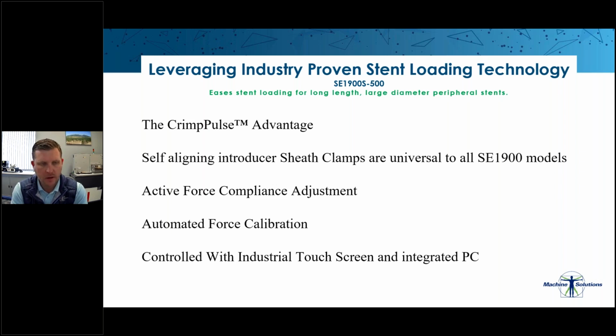A couple of the other benefits of our machine is automated force calibrations. This system uses a series of programmed force set points and interpolates force using an external force meter. This is standard process with all MSI segmental compression machines. And then lastly, all of our stent loading machines are controlled with industry leading touchscreen technology and integrated PCs. Obviously, the integrated HMI allows for easy access to machine features and programs, utilizes a PLC control system, and does have network connection capabilities.